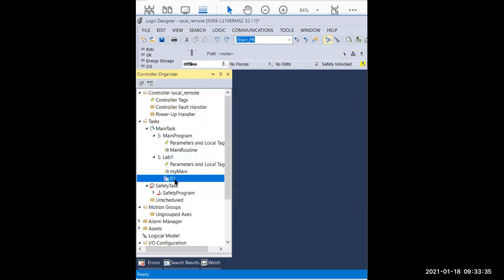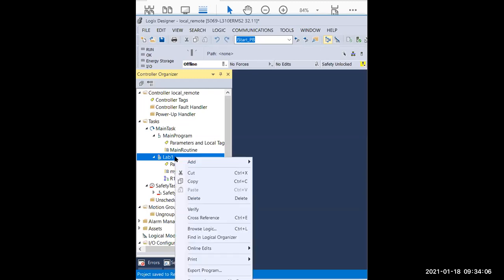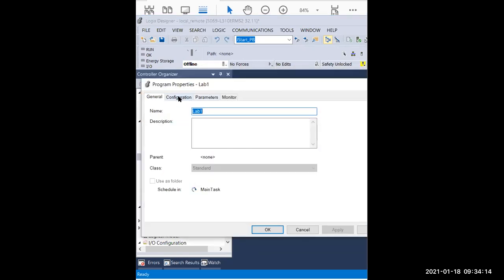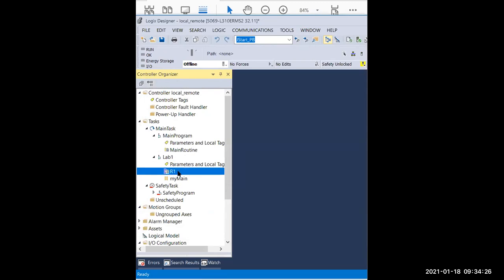If you happen to want to switch — you want to set up R1 as the main and My Main as a regular routine — you can switch the roles of these two routines. You can do that by setting up the property from the program, because program is one level above routine. Remember: task, program, routine. You just need to right-click the program, go into Properties at the bottom, choose Properties, and that's the configuration. There's a choice — currently it's My Main. You can choose R1 if you want. When you click OK, you can see R1 is switched to main, and My Main becomes a regular ladder logic routine.